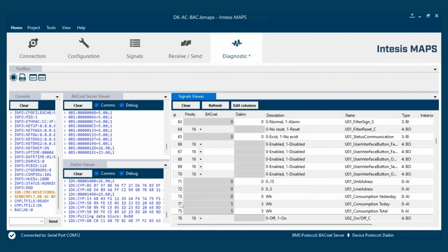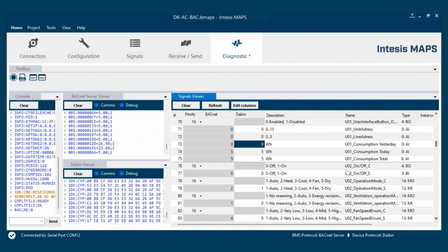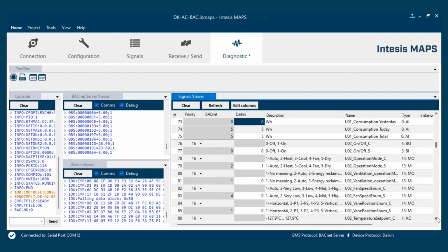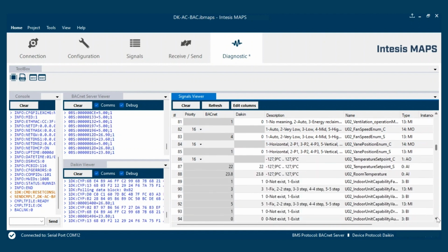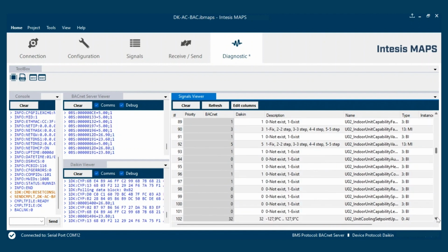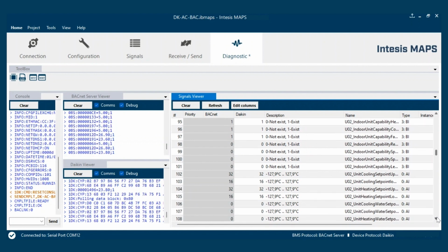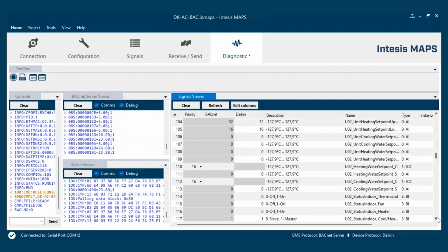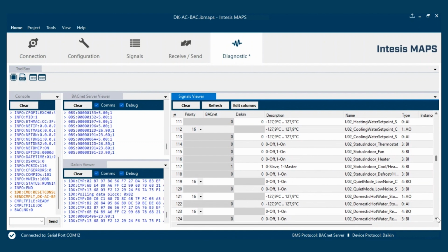Here we can see that indoor unit number 1 so far has consumed 5 watt-hours. Remember, this real demo consists of 1 energy meter and 4 indoor units connected to an outdoor unit. Our gateway receives the total consumption information from the outdoor unit, and the power estimation algorithm considers various factors to determine how the outdoor unit distributes the energy among the corresponding indoor units it serves.